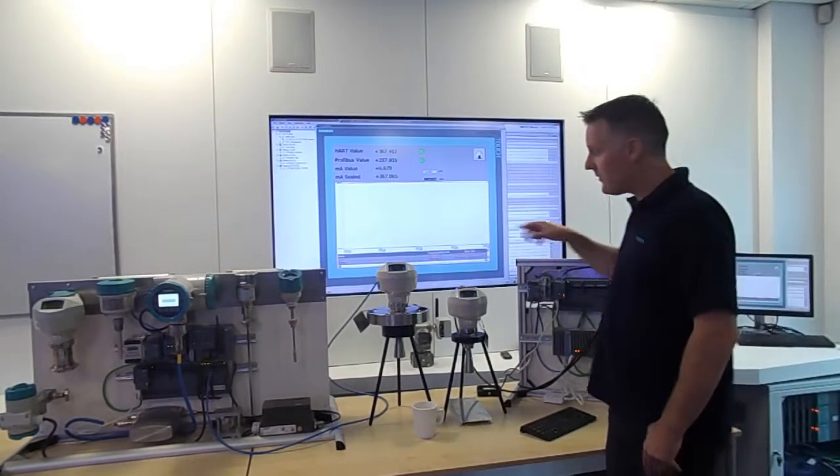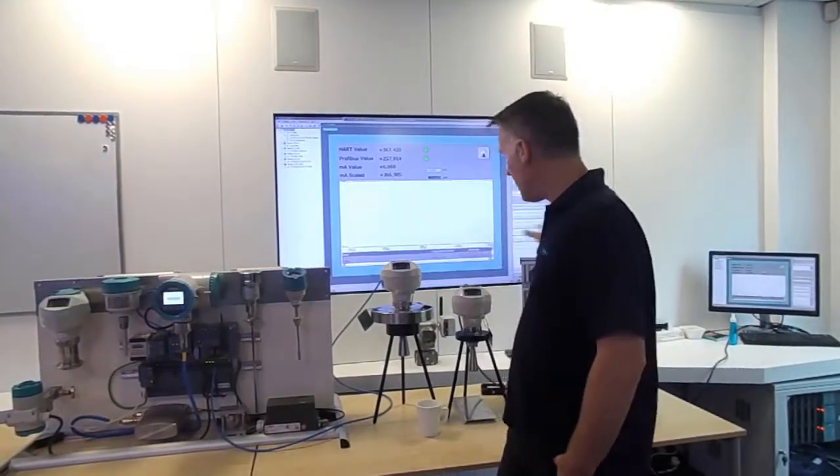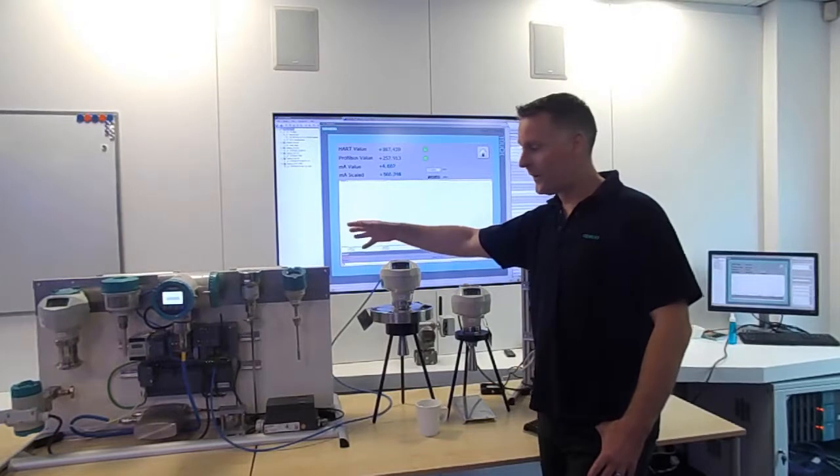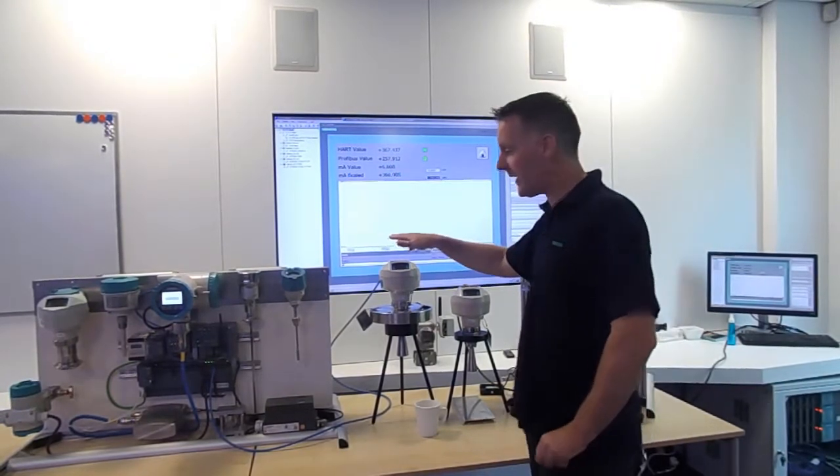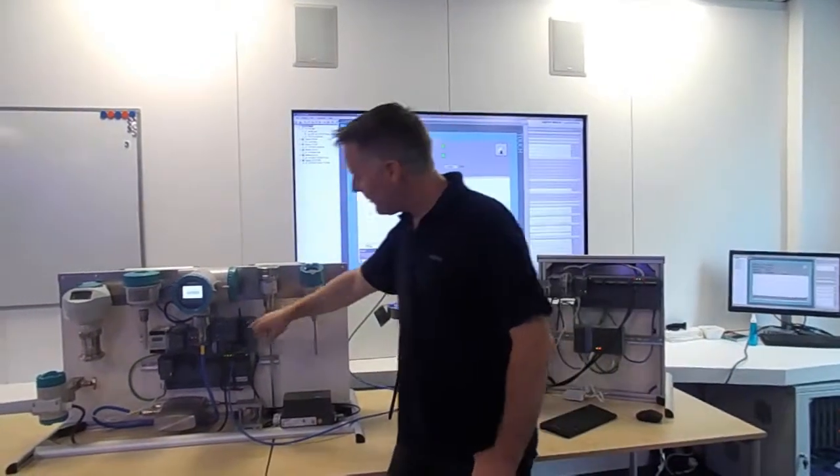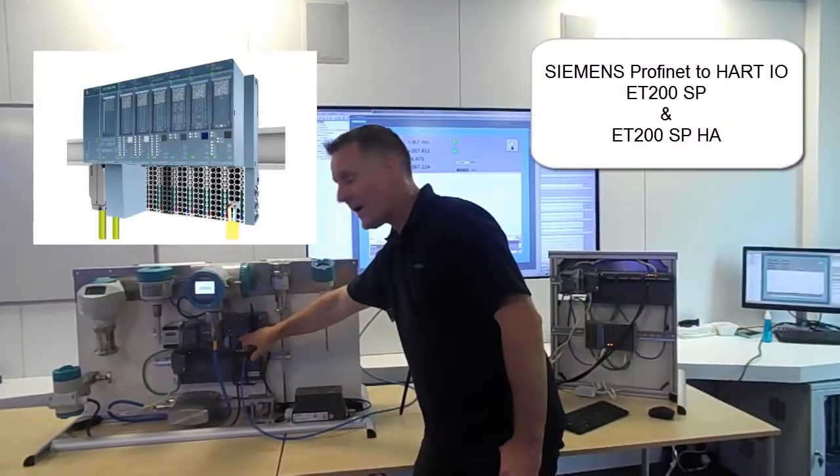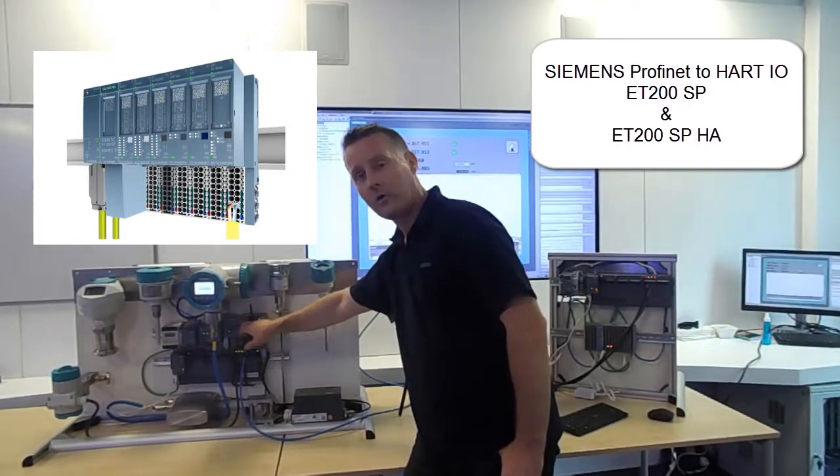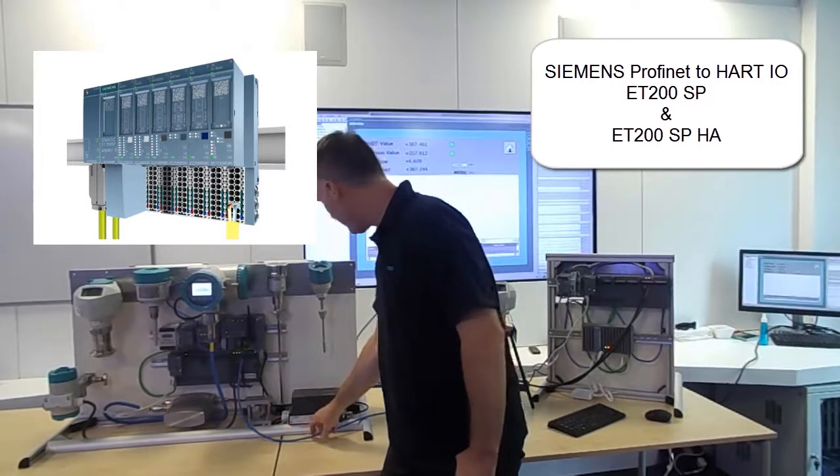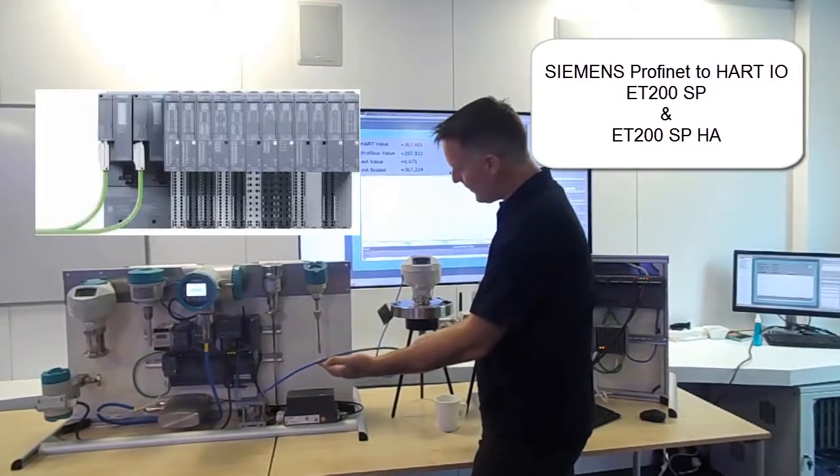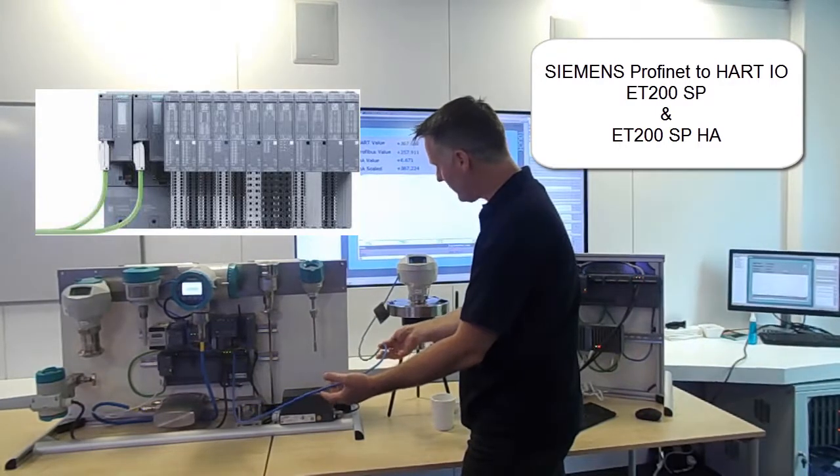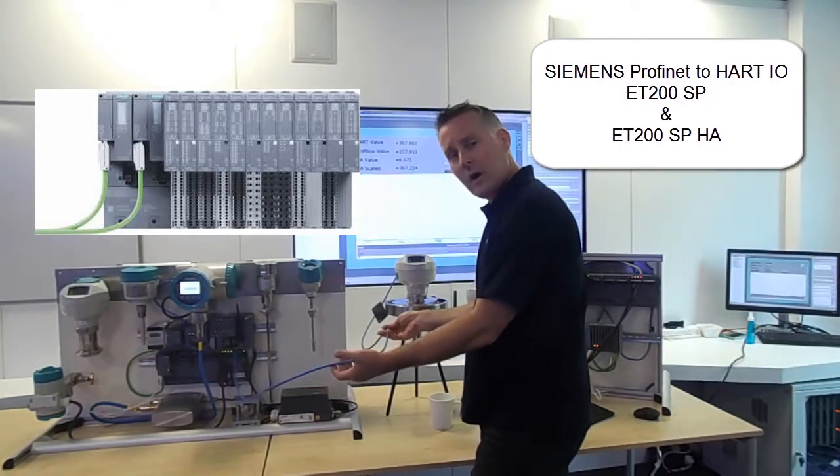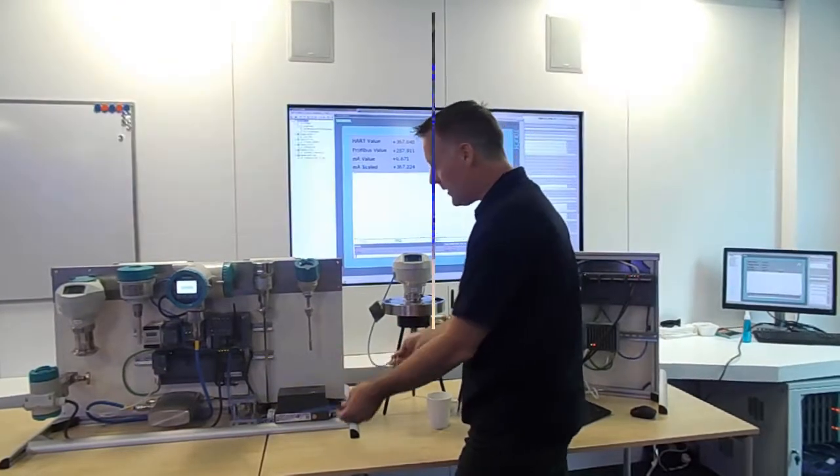So moving over to the 4 to 20, we're on the second part of the rig here. They're both connected together via one ethernet cable and it's ProfiNet or Profibus over that cable. We're taking this back into Siemens ET200ISP and it's an analog input card with HART on. So that enables us to bring back both values and again it's via a very short run of cable so we're not actually looking at noise interference here. We're just purely looking at how condensation or water ingress affects the signal.